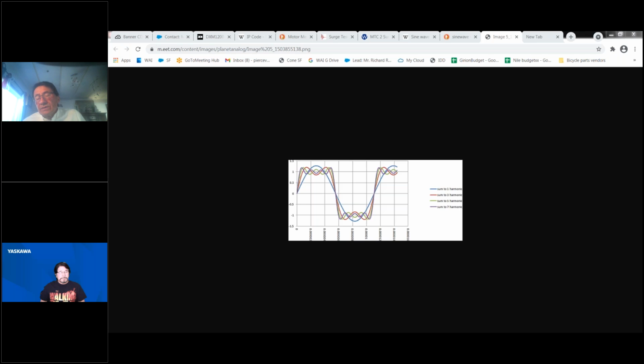And what it does is, did I say that right? Yes. It filters out all the high frequency DVDT voltage spikes and allows the low frequency, low pass filter, which is the 60 hertz signal, to pass through. So we still had failures. And with these DVDT filters, we're looking at the waveforms and we're saying, wait a minute, this isn't right.